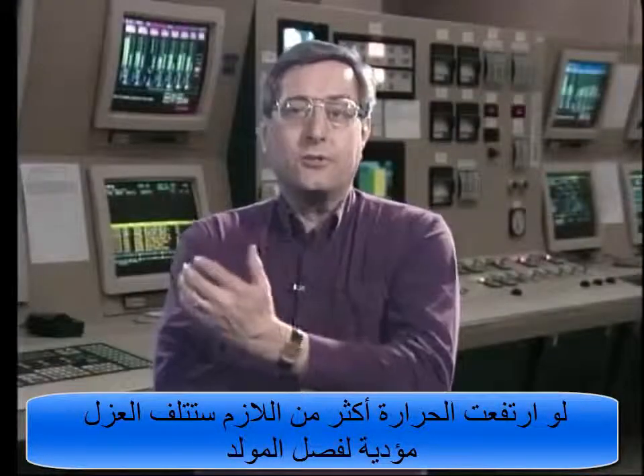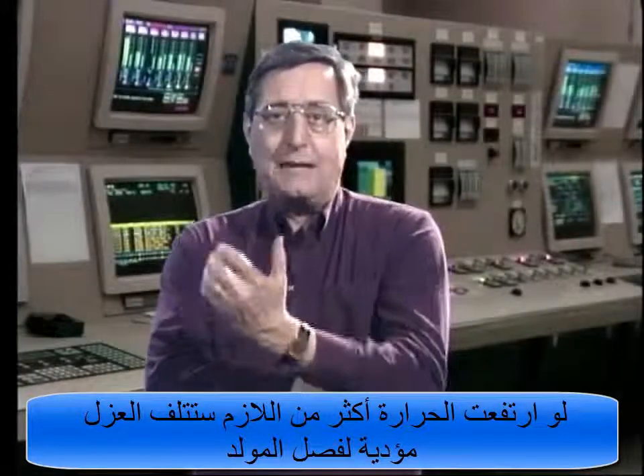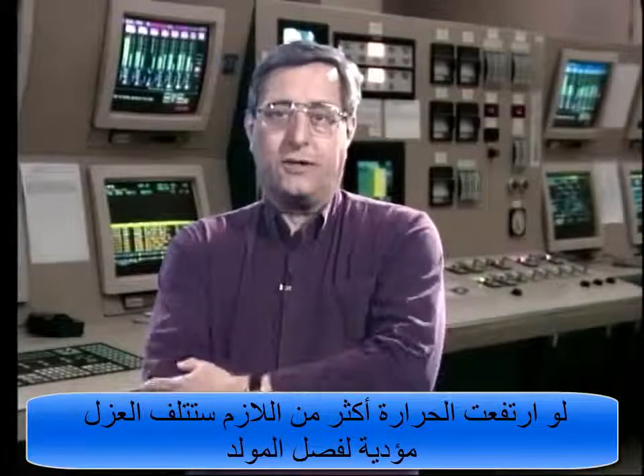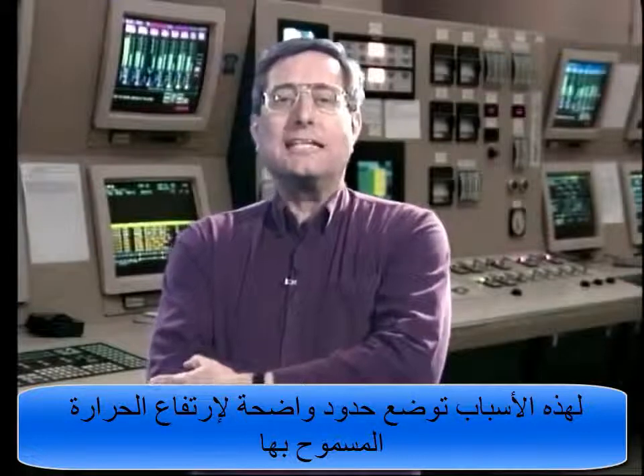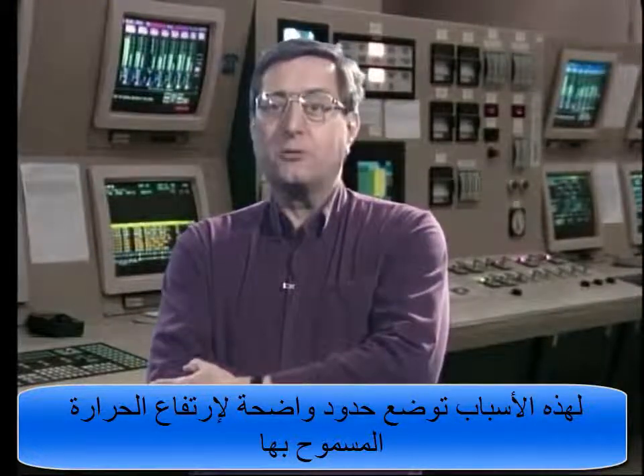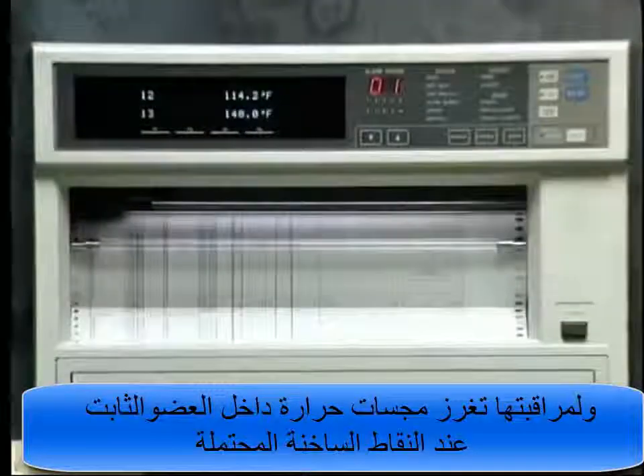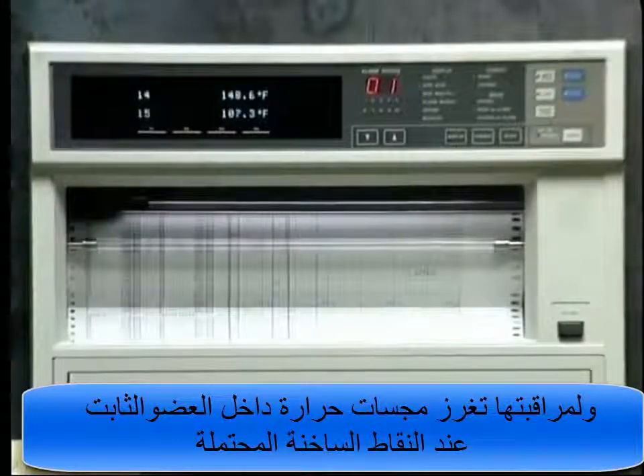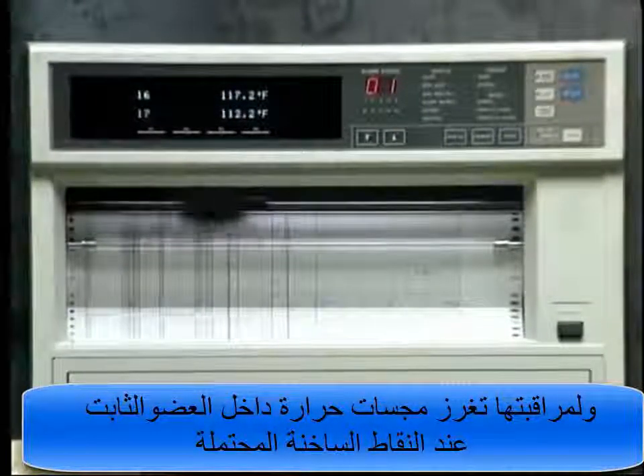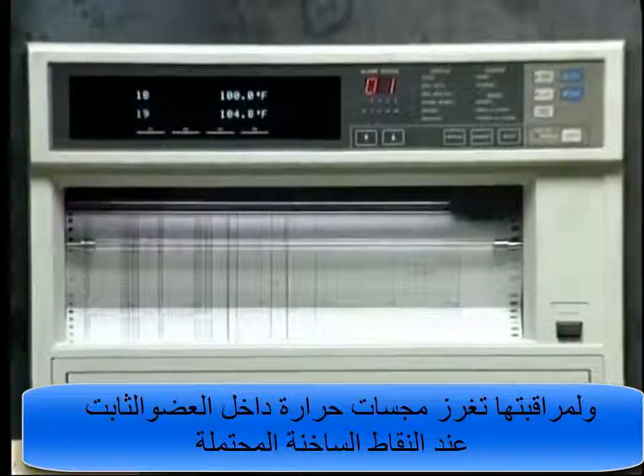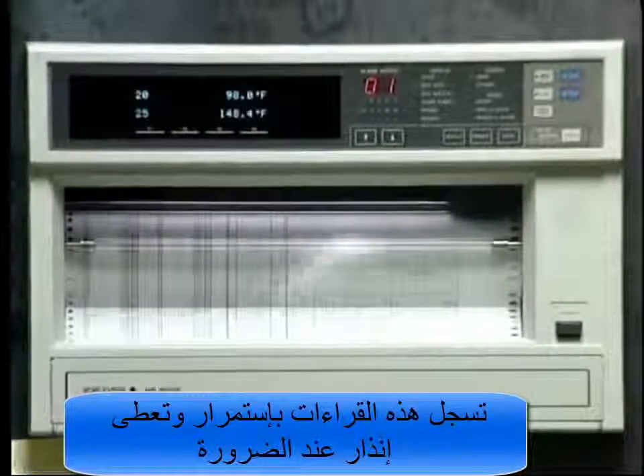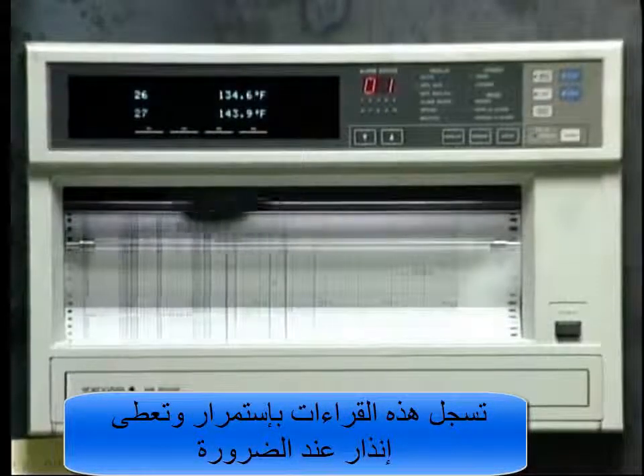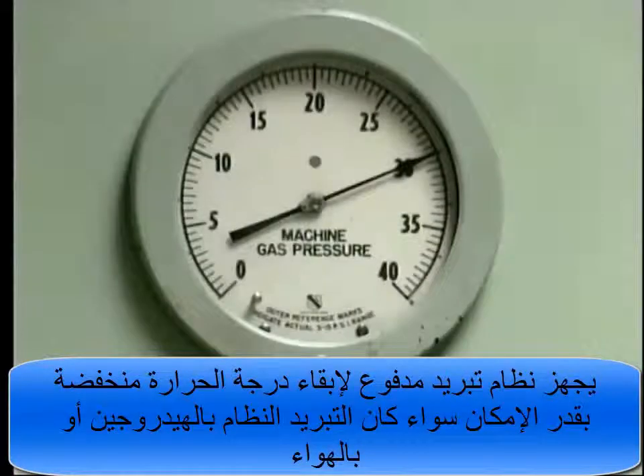If the internal temperature rises too high, it will damage the insulation and put the generator out of service. For this reason, distinct limits are placed on permissible temperature rise. In order to monitor this, temperature detectors are embedded in the stator windings at the anticipated hotspots. These readings are continuously recorded and alarmed when necessary. Forced cooling is employed to keep the temperature rise as low as possible, either by hydrogen cooling or air cooling.